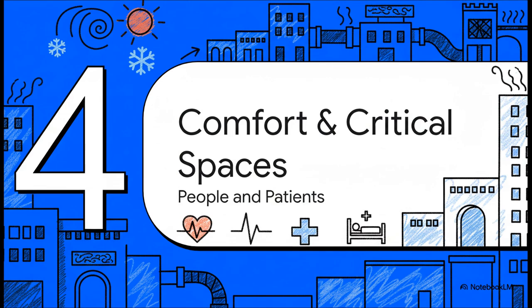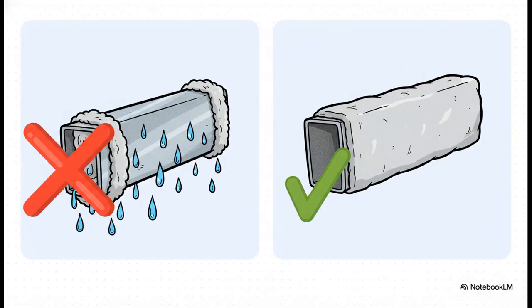This is about making sure the system not only works, but provides the right environment for people, and in the case of hospitals, a safe environment for patients. You ever see water dripping from ductwork? That's not just a mess to clean up. It's a giant red flag that your project has a problem. In the high humidity of the Gulf, it's a clear sign that your insulation isn't thick enough, or more likely, your vapor barrier isn't perfectly sealed. This is a visual failure of ASHRAE 55 comfort standards.